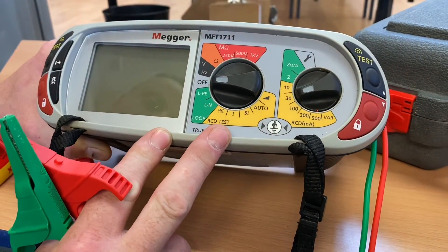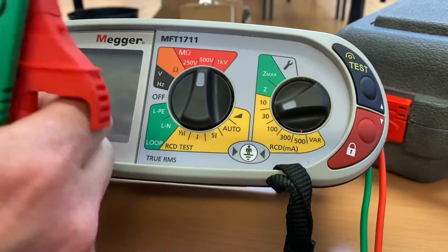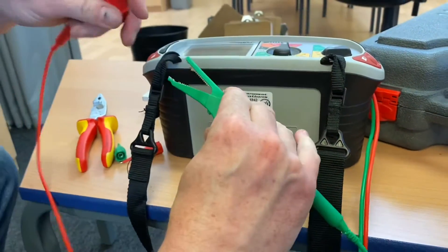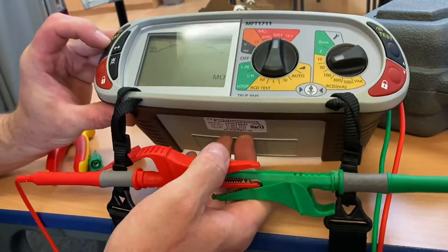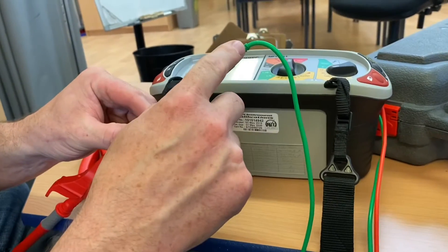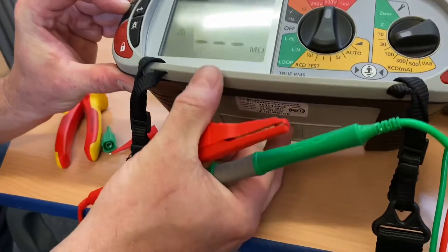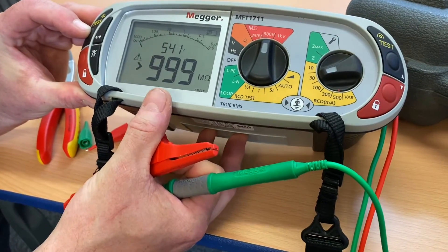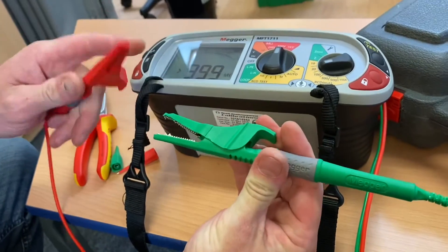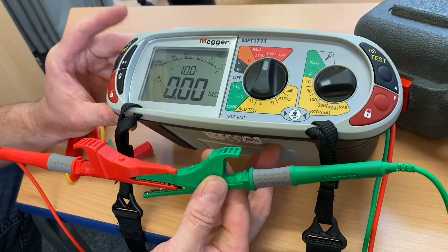We need to set our Megger MFT up for the insulation resistance test on the mega ohm scale, set to 500 volts DC. We should check the leads are good by bringing them together and pressing the test button to confirm a dead short. If a lead were broken, you'd get a false reading of greater than 999 megaohms, so always confirm a dead short before carrying out this test.